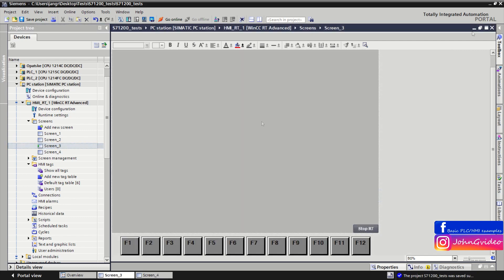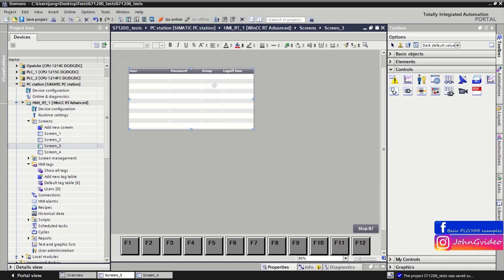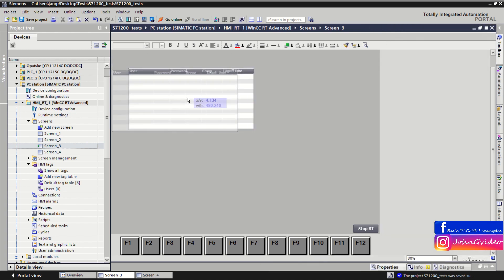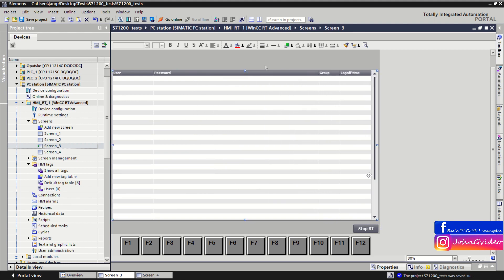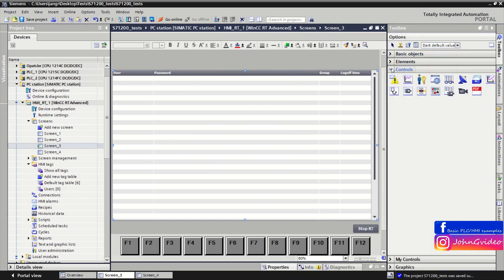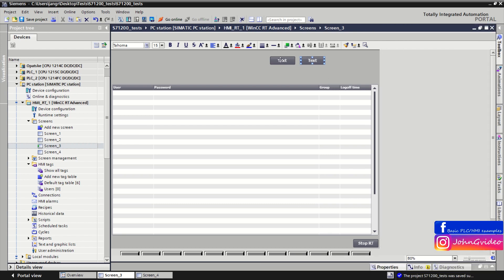First, we create a screen on which we insert the user view. With this user view you can administrate your users. Then we create two buttons — one for logging the user into the HMI and a second for logging the user out. This one will be for log in and this one for log out.